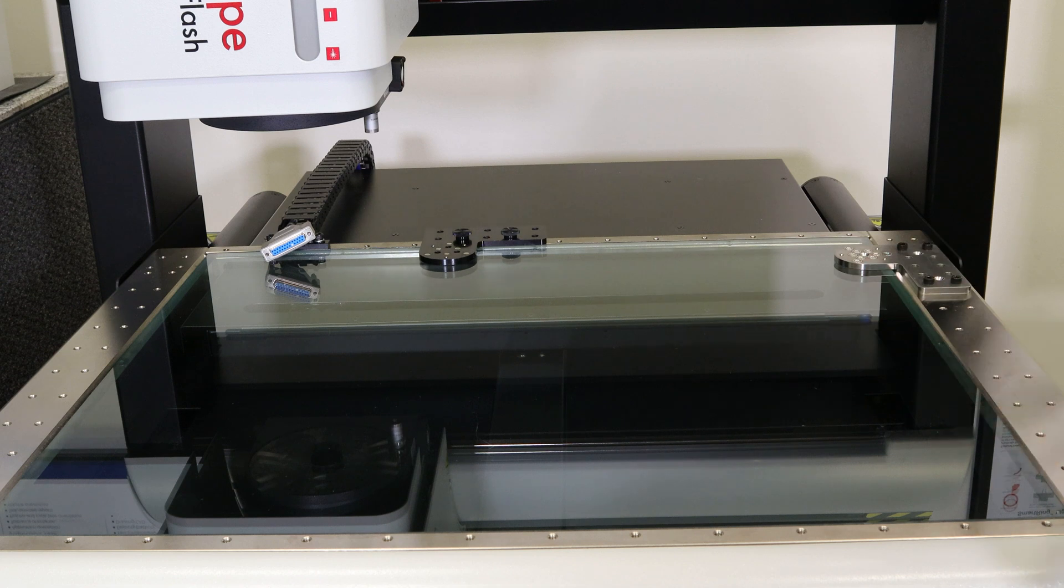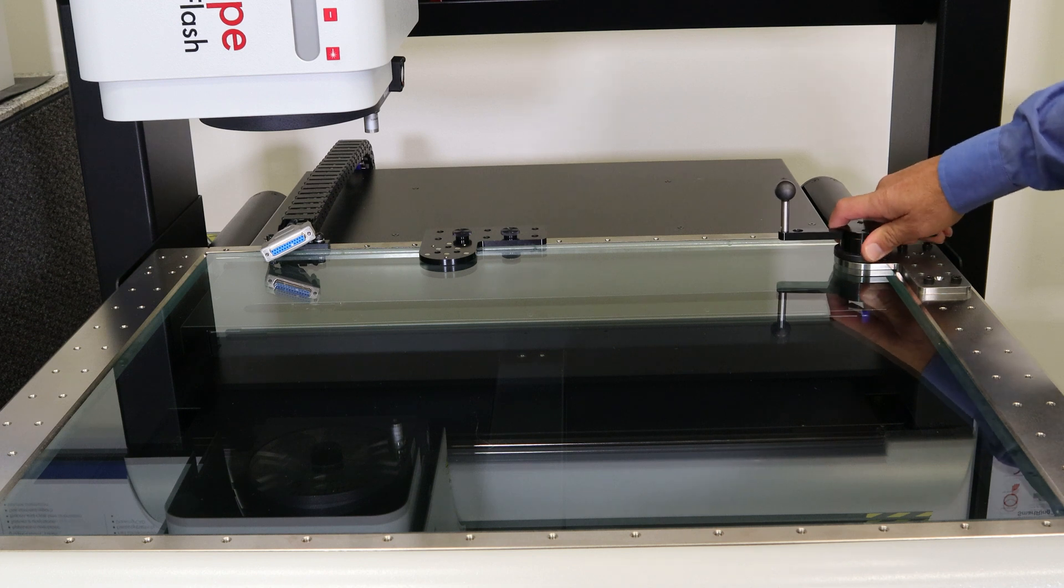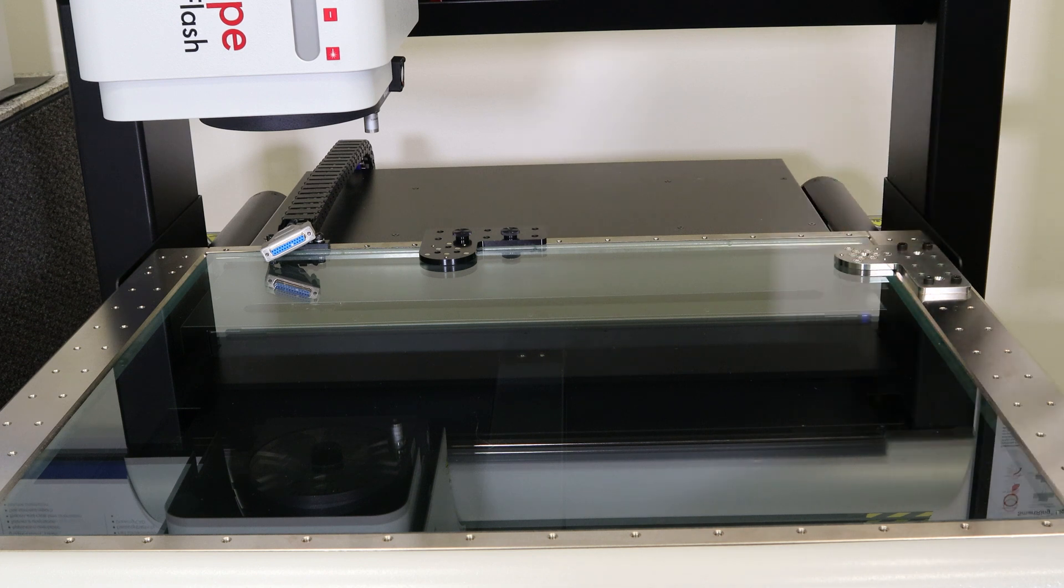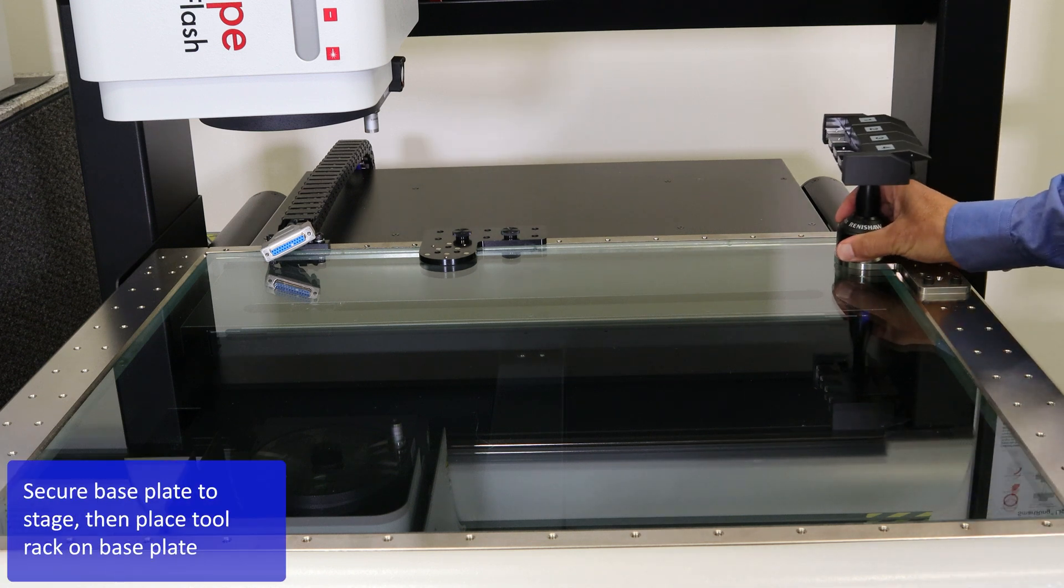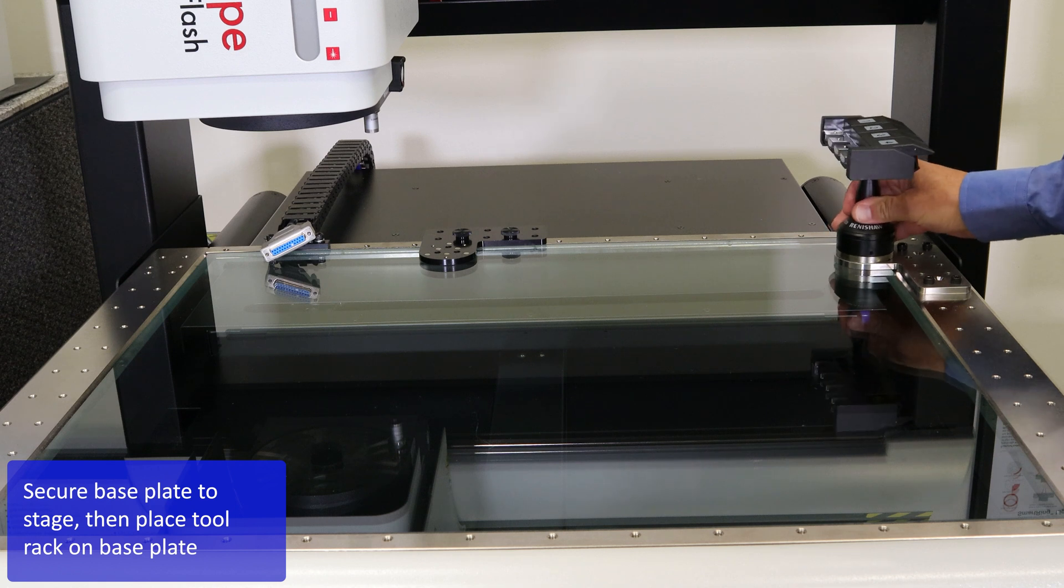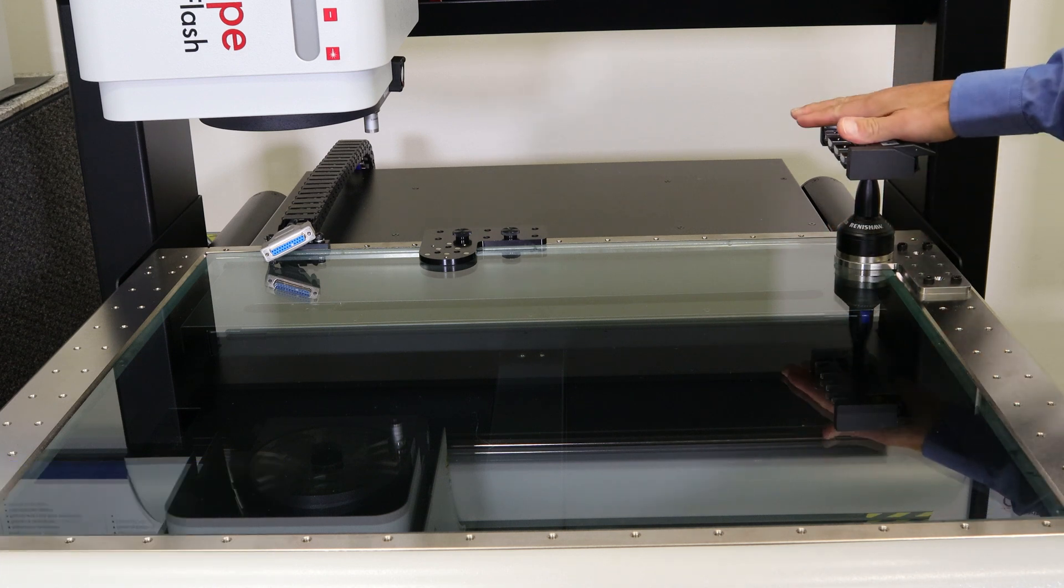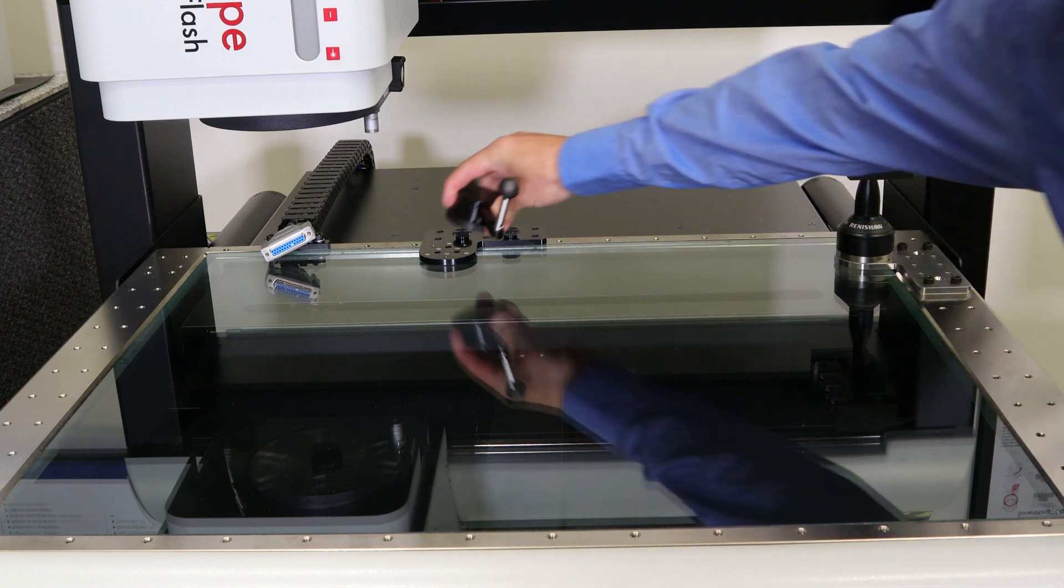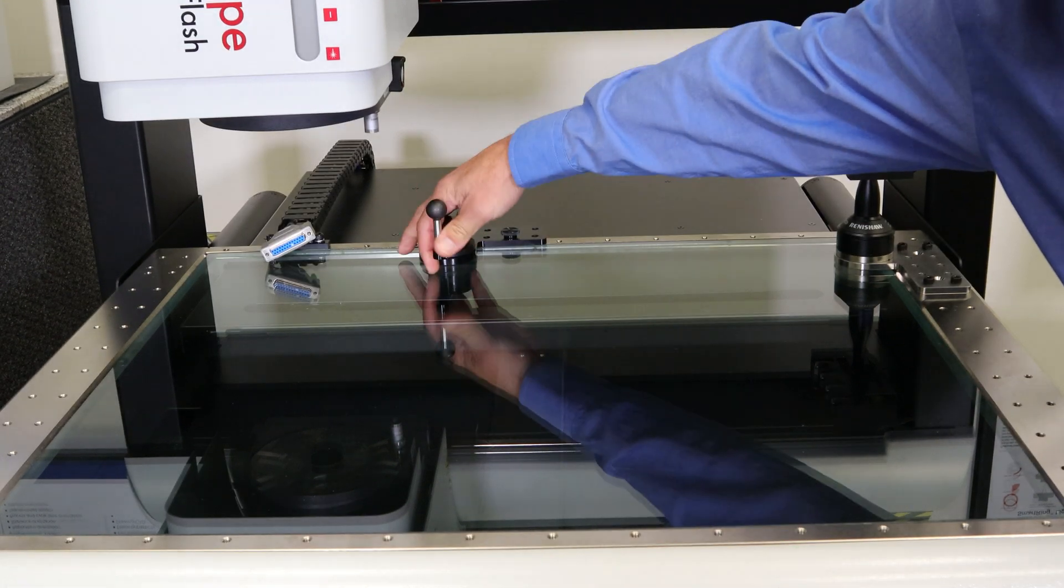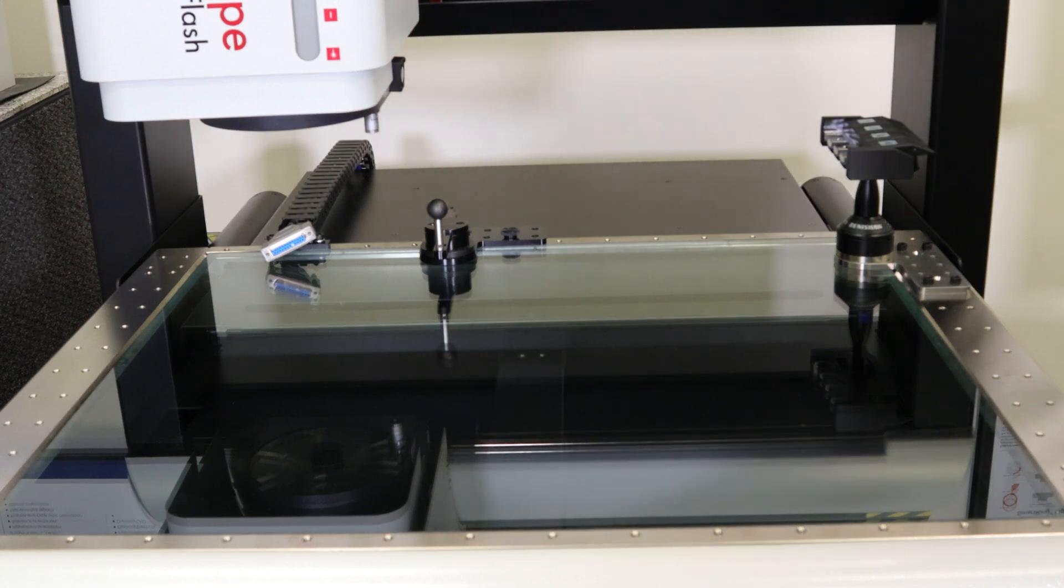The kinematic mount allows you to install a sphere, remove it when you're done qualifying your stylus, and then install your tool rack. Since this machine has two kinematic mounts, we're going to use one for the tool rack and the second for a qualification sphere. Make sure it's snapped in the right spot and shouldn't move anymore.